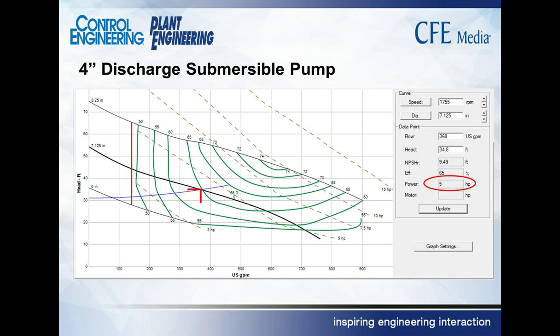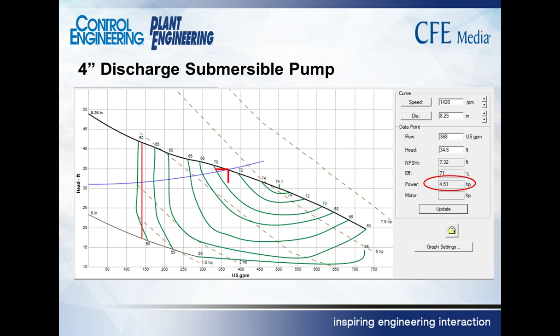What if instead of trimming the impeller, we changed the speed of the pump and left the bigger impeller on? Can you see that that would move the operating point, that's 5 horsepower, up to there. There it is with the same operating point, but it moved it up onto the higher diameter impeller, but lowered the speed. The speed is now 1420 RPM, and we reduced the power from 5 horsepower down to 4.5 horsepower. So we saved a half of a horsepower. Some savings, potentially, but not near what we saw with the system that had the much steeper curve.